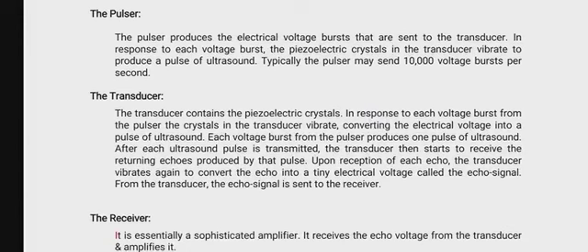Now the pulser produces the electric voltage bursts that are sent to the transducer. In response to each voltage burst, the piezoelectric crystal in the transducer vibrates to produce a pulse of ultrasound. Typically, the pulser may send like 10,000 voltage bursts per second, like poof, poof, poof, poof, 10,000 in 1 second. Now, this transducer contains the piezoelectric crystals. In response to each voltage burst from the pulser, the crystal vibrates, converting the electrical voltage into a pulse of ultrasound. So it is at the transducer that those bursts of voltage, up to 10,000, are converted into ultrasound, into sound.